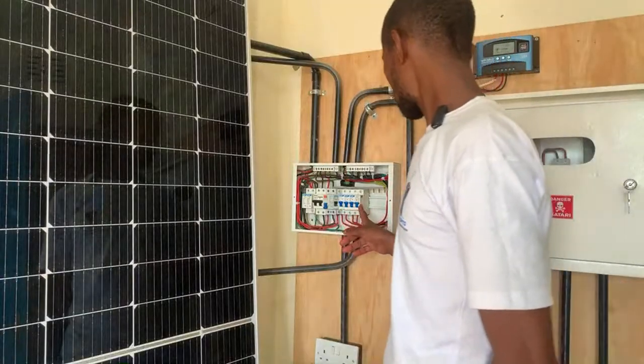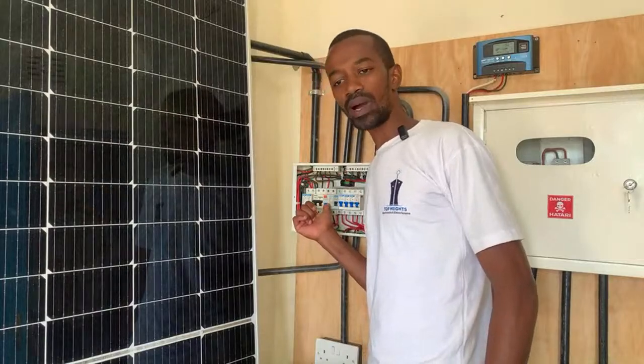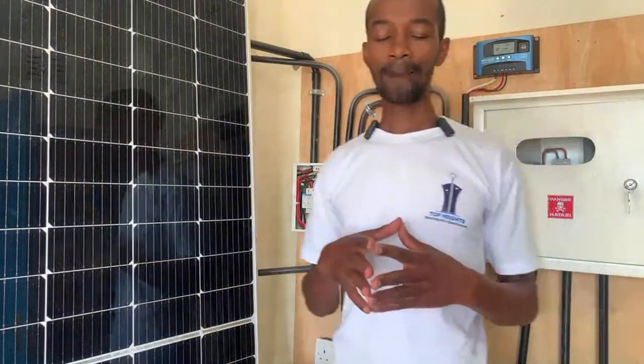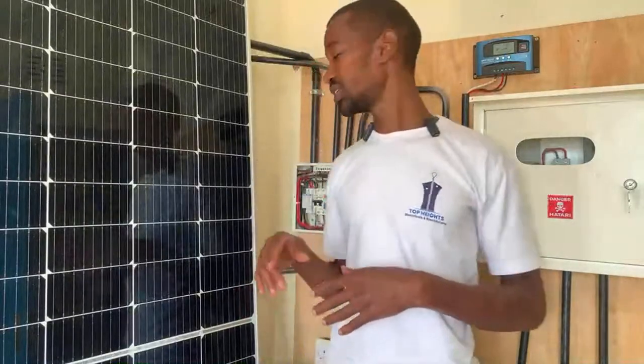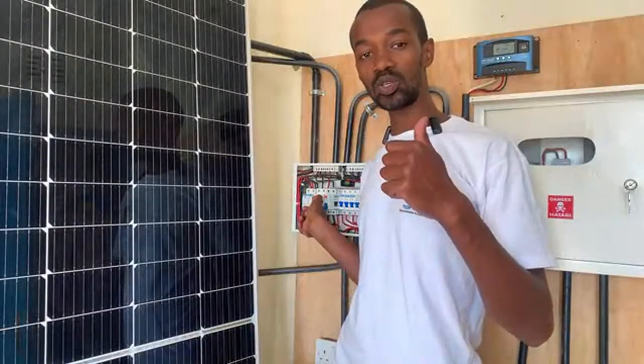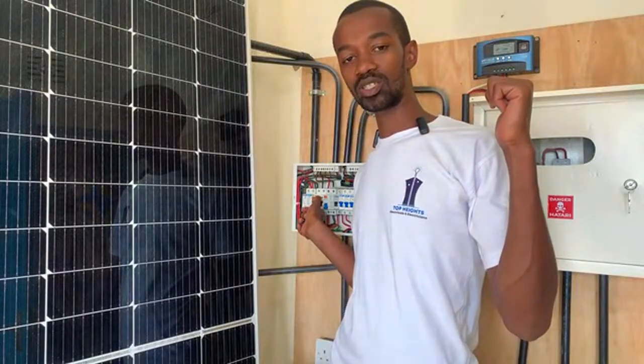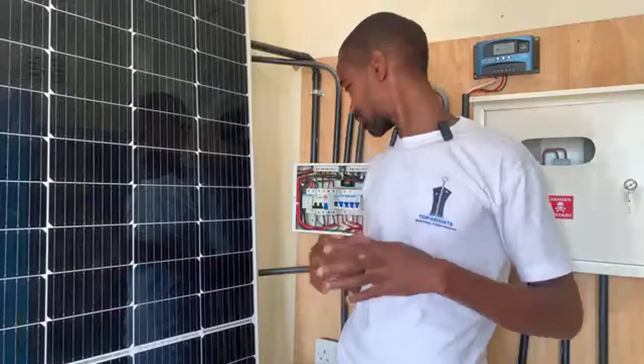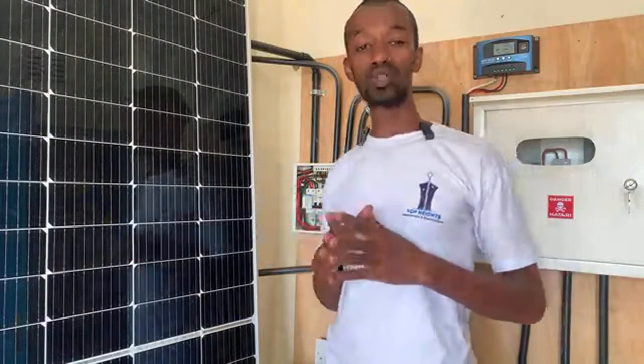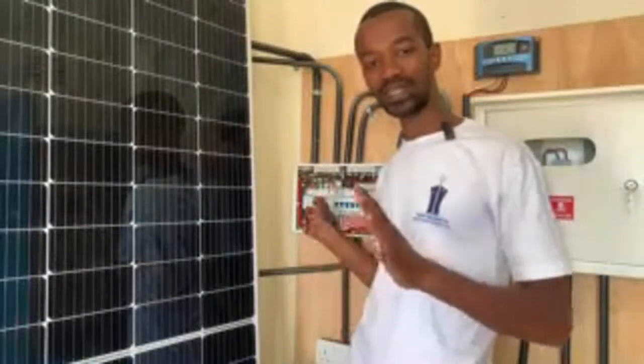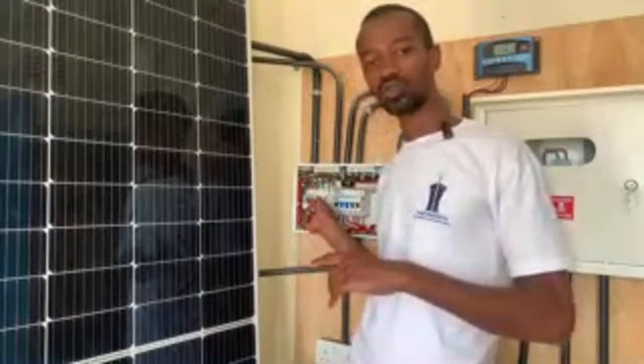So that is about the connection at the consumer unit, and we have said that you must ensure that this connection here is tightly done. Now, another consideration is the main switches, and I will also be touching on the main switch that is located in the meter box in a short while before we conclude our live session today. This main switch is supposed to cut the supply of electricity in case there is an overcurrent. The second main purpose of our main switch is that it is a point of isolation. So in case you want to cut off electricity supply in that entire electrical installation, this main switch will definitely do the good job.